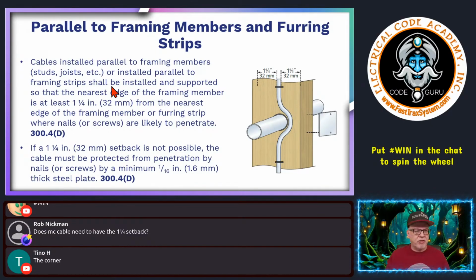All right, so let's finish this thought real quick. Parallel to framing members and furring strips: cables installed parallel to framing members, studs, joists, whatever, or installed parallel to furring strips, shall be installed and supported so that the nearest edge of the framing member is at least 1 1/4 inches, 32 millimeters, from the nearest edge of the framing member or furring strip where nails or screws are likely to penetrate. So if you're in a basement and you're furring it out and finishing it off, and you run your cable down the side of the furring strips, you run the risk of actually penetrating.